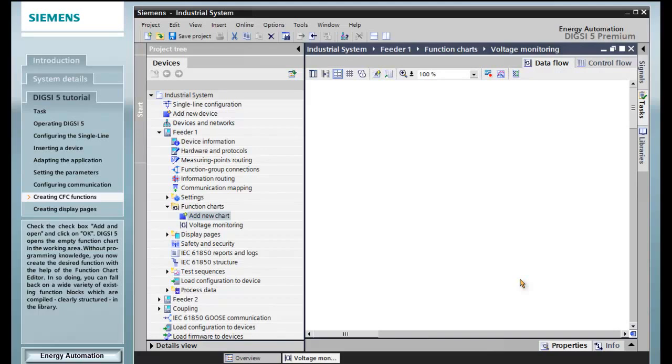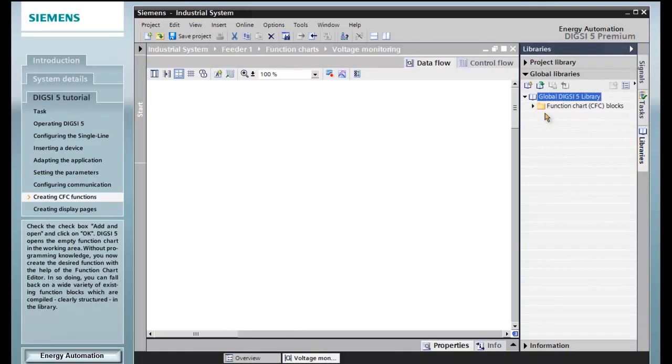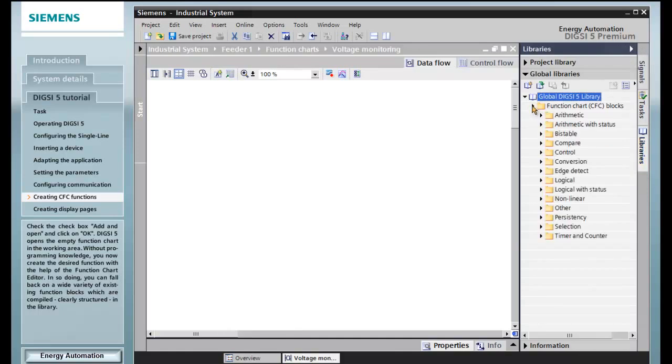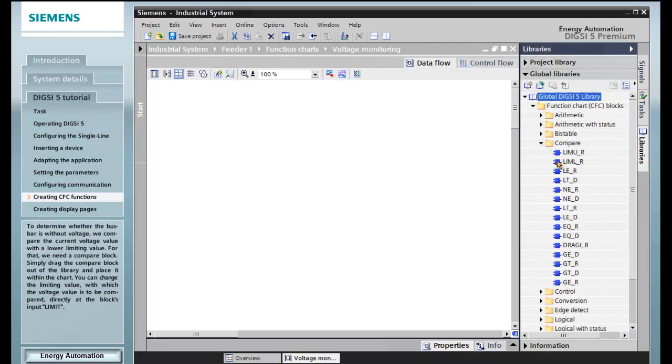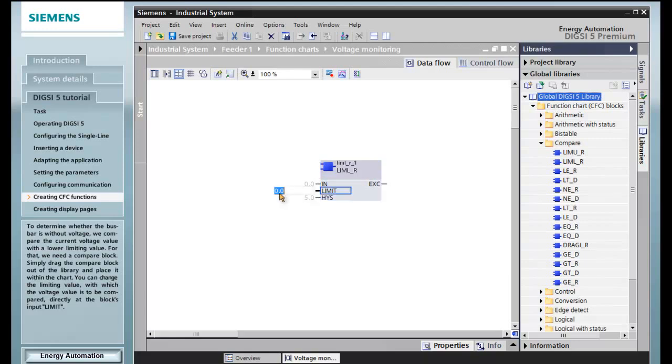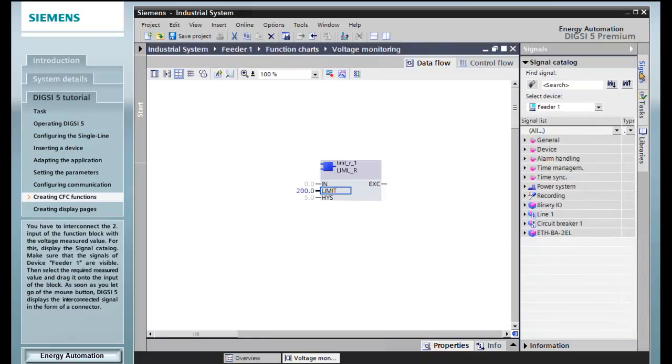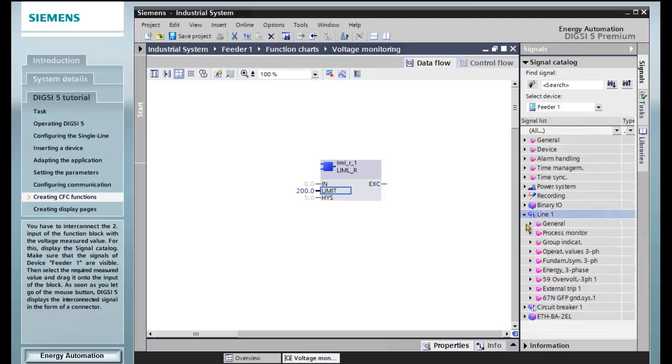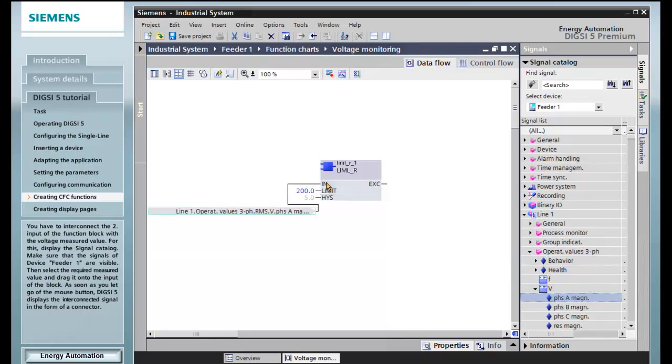Without programming knowledge, you now create the desired function with the help of the function chart editor. In so doing, you can fall back on a wide variety of existing function blocks which are compiled, clearly structured, in the library. To determine whether the bus bar is without voltage, we compare the current voltage value with a lower limiting value. For that, we need a compare block. Simply drag the compare block out of the library and place it within the chart. You can change the limiting value, with which the voltage value is to be compared, directly at the block's input limit. You have to interconnect the second input of the function block with the voltage measured value. For this, display the signal catalog. Make sure that the signals of device feeder 1 are visible. Then select the required measured value and drag it onto the input of the block. As soon as you let go of the mouse button, DIGSI 5 displays the interconnected signal in the form of a connector.